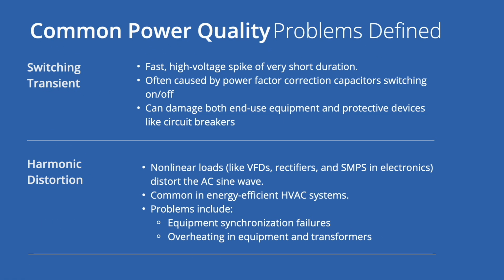Switching transient. Fast, high voltage spike of very short duration, often caused by power factor correction capacitors switching on and off, can damage both end-use equipment and protective devices like circuit breakers. Harmonic distortion. Nonlinear loads like VFDs, rectifiers, and SMPS in electronics distort the AC sine wave, common in energy-efficient HVAC systems. Problems include equipment synchronization failures, overheating in equipment and transformers.